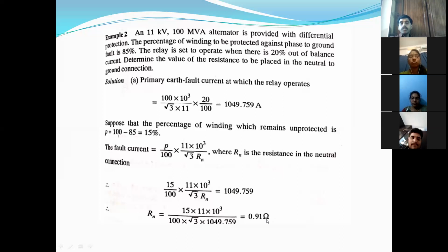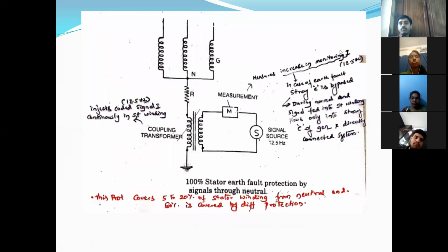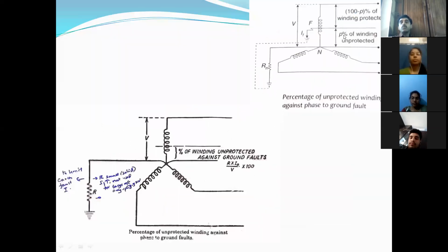That means using this simple formula, you can calculate the percentage of winding unprotected, or the value of the R to be included in the neutral to ground connection. These are simple problems to solve. Just using this simple formula, we can get any value we want. We need to calculate the I0 value, the R value, and the P value.